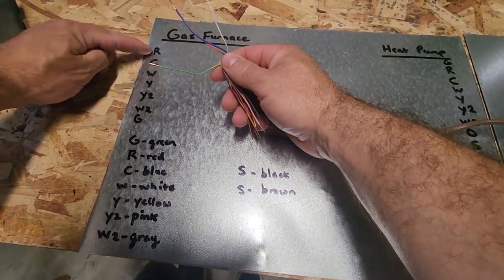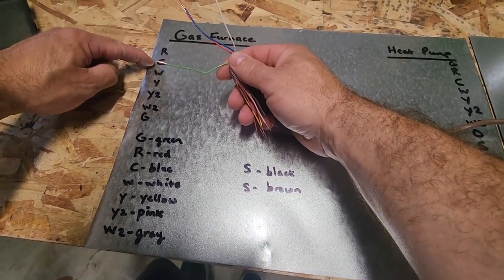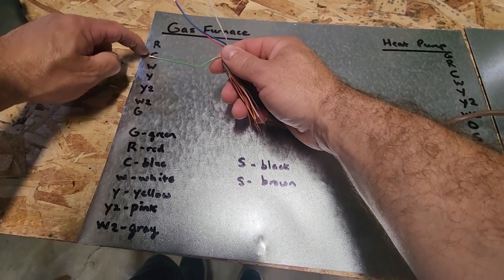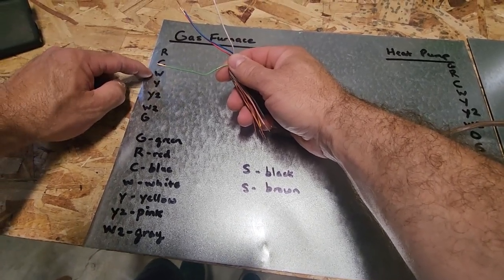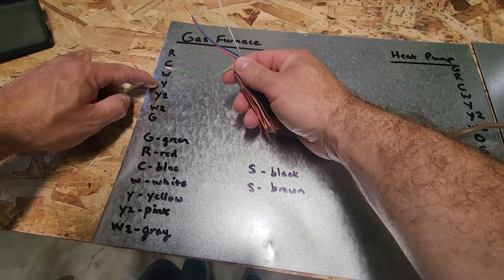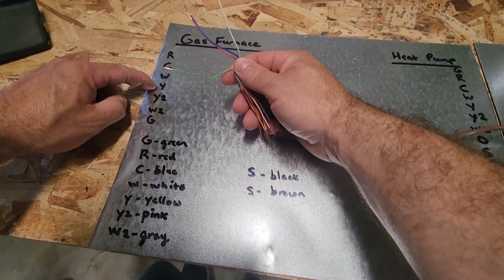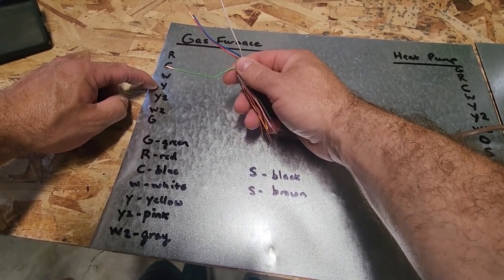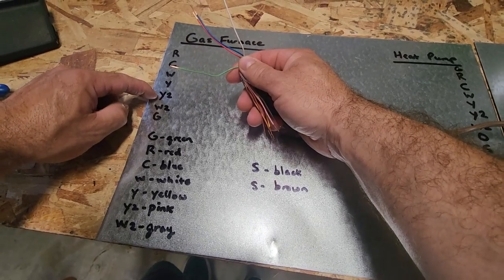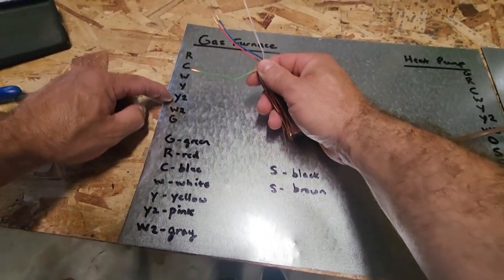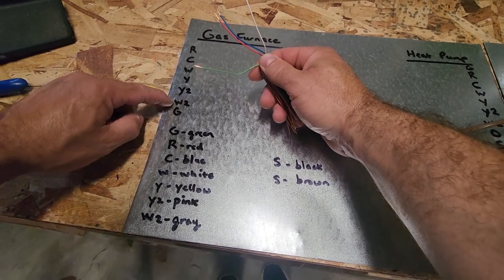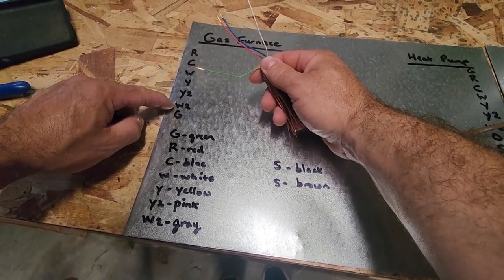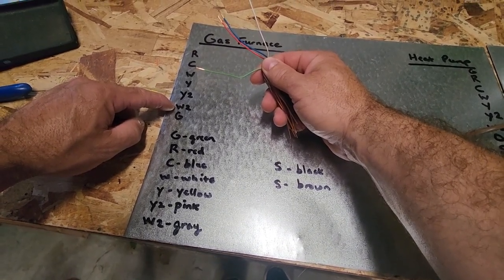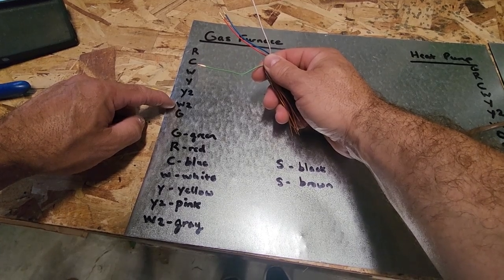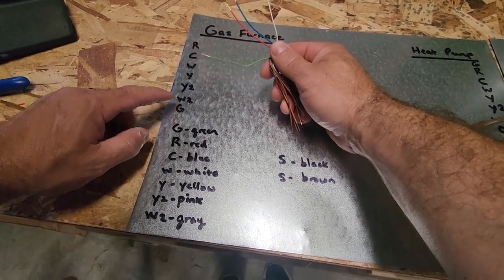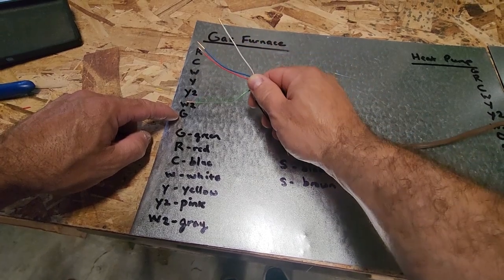So you have 24 volts, and 24 volts common, that completes your 24 volt circuit. W is heat. Y is going to be your yellow wire, that's cooling. Y2 would be if you had a second stage of cooling on a 2-stage air conditioner. W2 would be if you had a second stage of heat on your gas furnace. I'll tell you what wire we'll use for that. And then G, your green, is your fan.